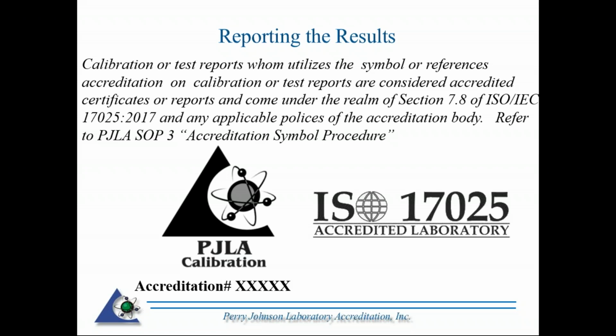So reporting the results. Whenever a test or calibration report utilizes the accrediting body symbol, or references laboratory accreditation to the standard 17025, it would be considered an accredited report, and it was intended to come under the realm of the laboratory's accreditation. Also, there are any applicable policies and procedures that your accreditation body may have in place, such as the utilization of the symbol for PJLA. That's PJLA SOP 3. So again, any use of the logo on a test or calibration report is an indication that that report is intended to come under your organization's scope of accreditation.